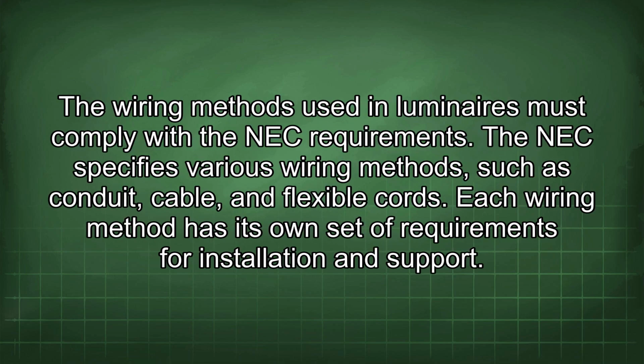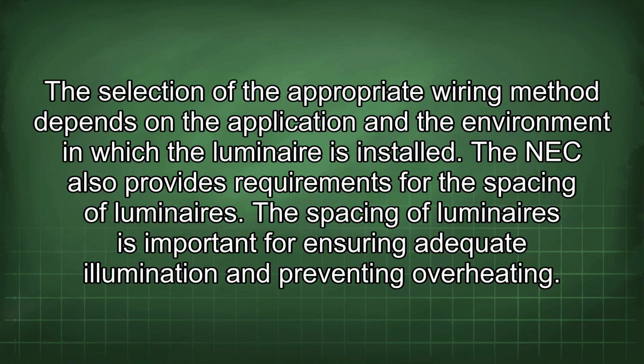The wiring methods used in luminaires must comply with the NEC requirements. The NEC specifies various wiring methods such as conduit, cable, and flexible cords. Each wiring method has its own set of requirements for installation and support. The selection of the appropriate wiring method depends on the application and the environment in which the luminaire is installed.